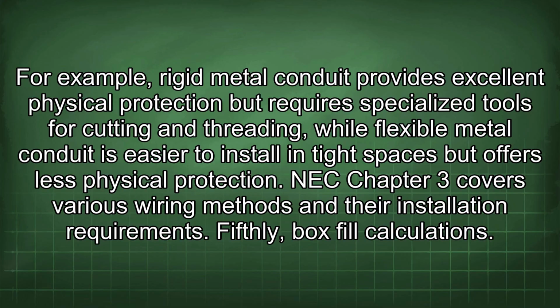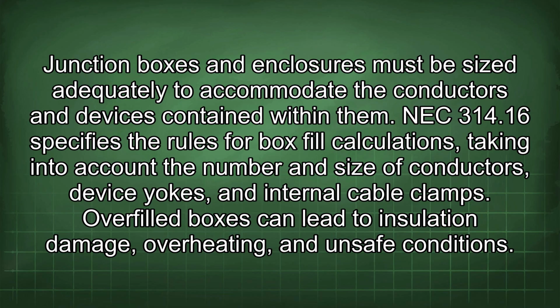Fifthly, box fill calculations. Junction boxes and enclosures must be sized adequately to accommodate the conductors and devices contained within them. NEC 314.16 specifies the rules for box fill calculations, taking into account the number and size of conductors, device yokes, and internal cable clamps. Overfilled boxes can lead to insulation damage, overheating, and unsafe conditions.